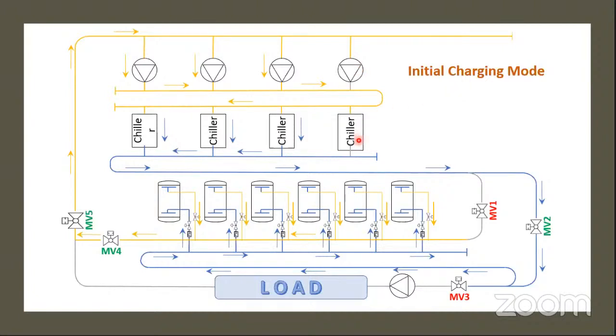Here we have primary pumps, chillers, secondary pumps, and thermal storage tanks. These are many, by the way; there can be two, three, four tanks, or a single one. In our initial charging mode, the chilled water is coming from the chiller and going here, and as I said earlier, the charging happens from the bottom. The warm water which is already present inside the tank comes into this header and is sent back to the suction of the primary pump to get cooled again. That's your initial charging cycle, in which load does not come into play, as secondary pumps do not come into play.